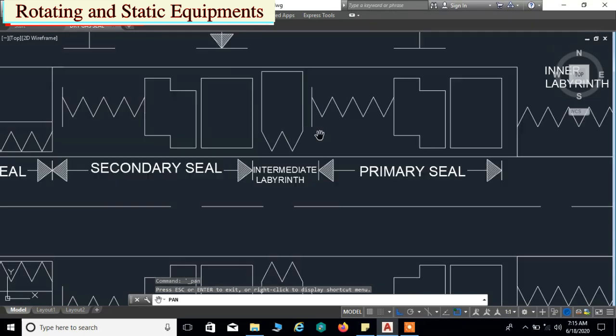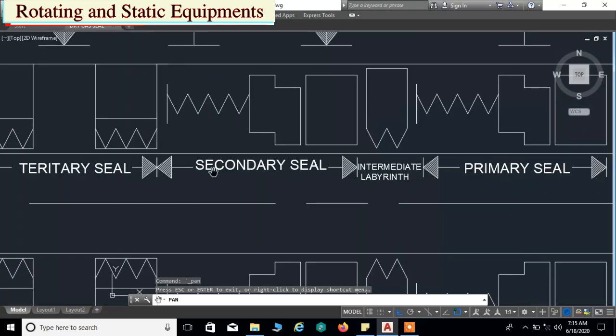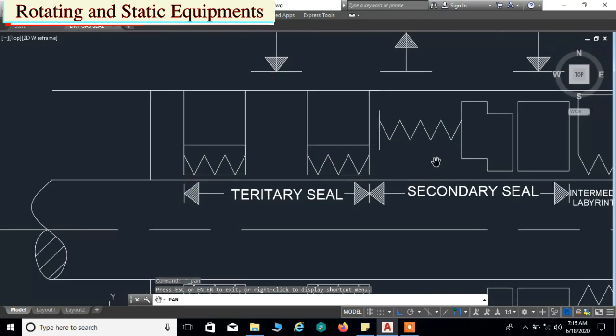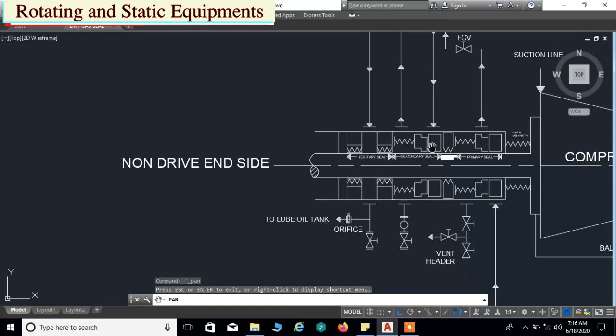After that we have an intermediate labyrinth seal. Then the second unit is called the secondary seal. It consists of a set of seal ring, mating ring, secondary sleeve, secondary housing, secondary retainer, secondary static elements, and springs. After the secondary seal we have the tertiary seal. These are all the units from the non-drive end side.